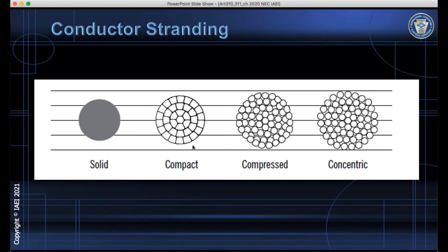Now it's important to realize it doesn't matter which of these stranding methodologies you use. The ampacity is based on the AWG or circular mill size. So it doesn't make a difference if it's solid, compact, compressed, or concentric when you're calculating ampacity.